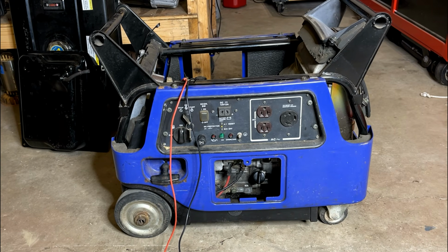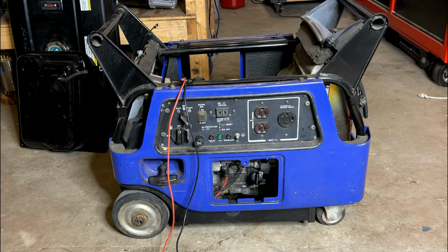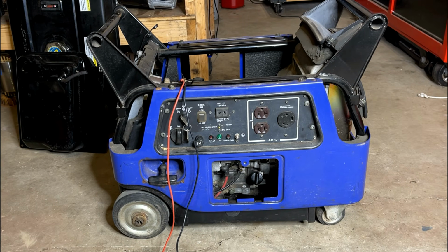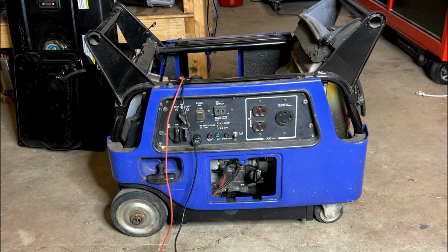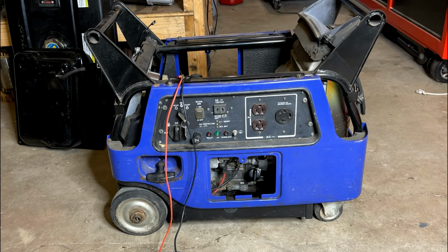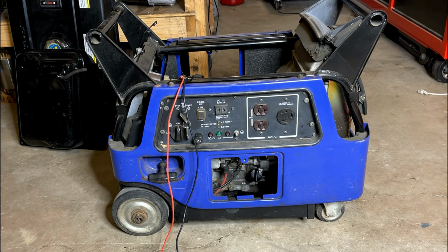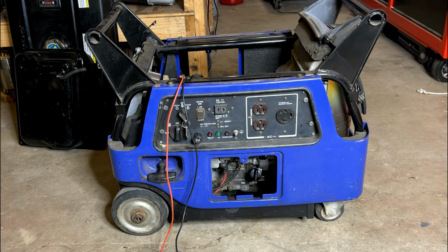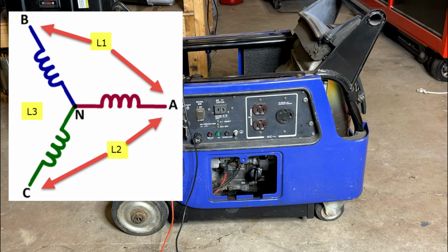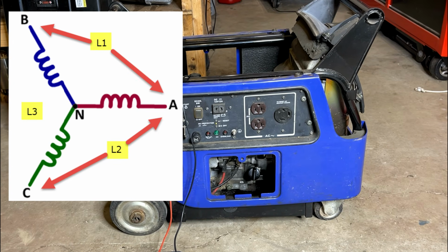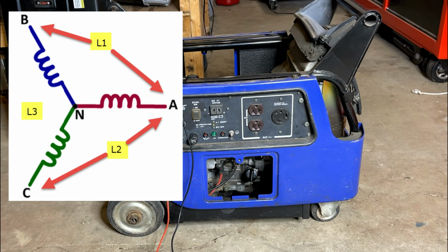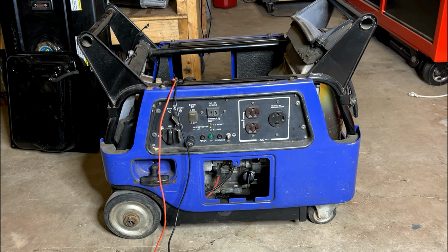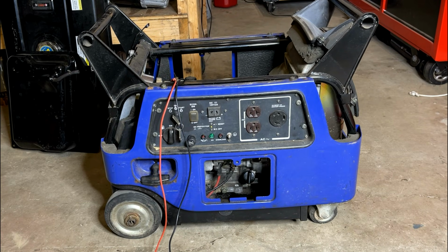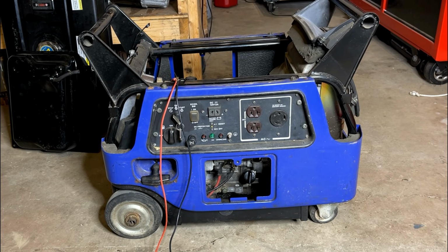The confusing part is that the manual said to only check 2 of the 3 legs, and that got me thinking as to why. But when it comes down to it, this is in a Y configuration, and if you check any 2 legs, you've actually checked all 3 coils and all 3 yellow wires coming out. So checking the third one is kind of redundant, but that doesn't explain the reading I got.